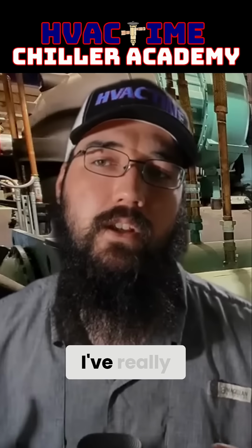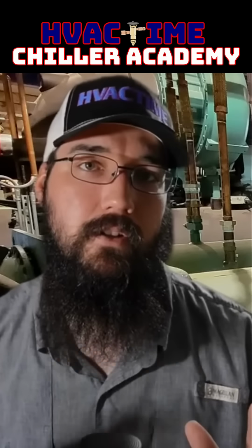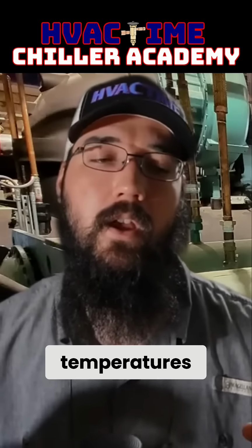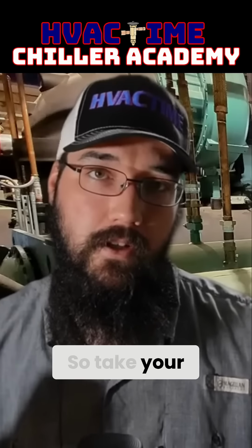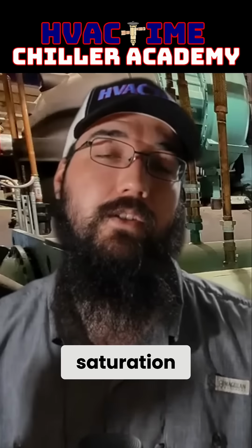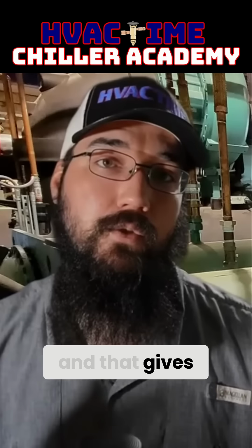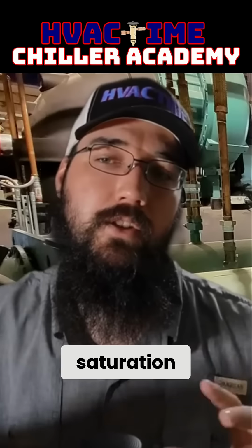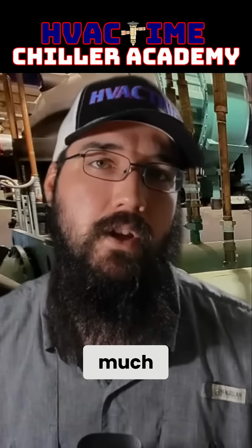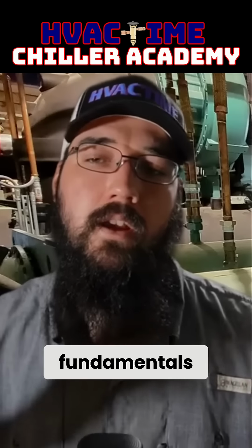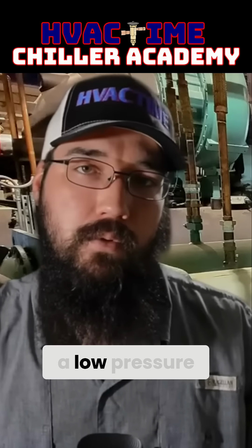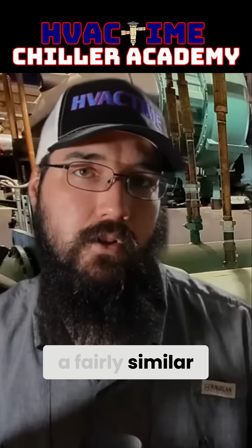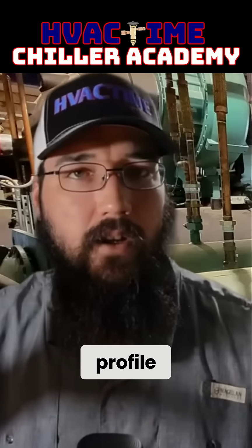Now, recently, I've really started embracing the saturation methodology, where it's not based off of pressure, but the saturation temperatures. So take your condenser saturation and your evaporator saturation, subtract those from each other, and that gives you your saturated lift value. And when you take that approach from a saturation, then the pressures themselves really don't matter so much, because the core fundamentals, whether you're talking a high pressure YK or a low pressure CVH, both of them have a fairly similar surge profile, if you will.